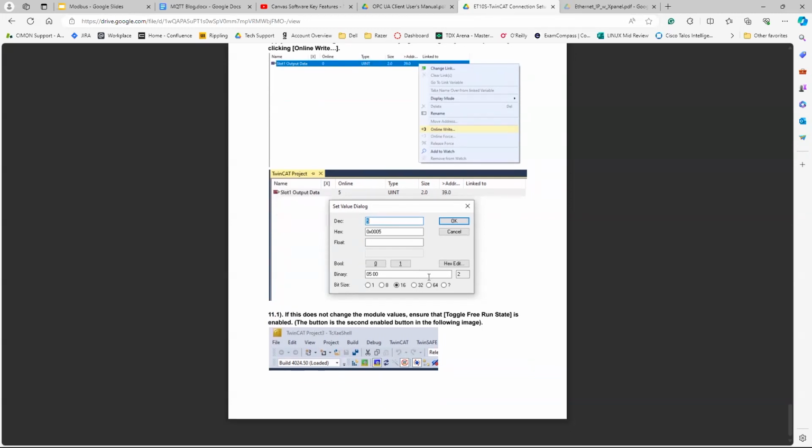And that's basically all you have to do. So again, let's refresh through those steps. All I did was download the CIMON software. I create my ESI file by declaring which IO modules from CIMON I'll be using, and then I don't need the CIMON software ever again. I take the ESI file, I import it into my EtherCAT master, and then I scan the device, make sure I can detect it, and then I can control the IO from there.